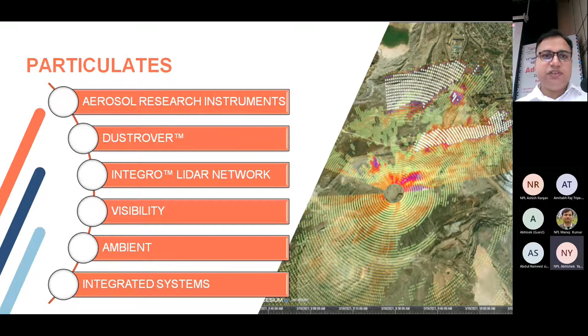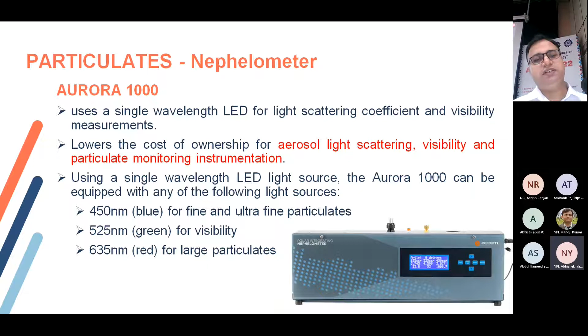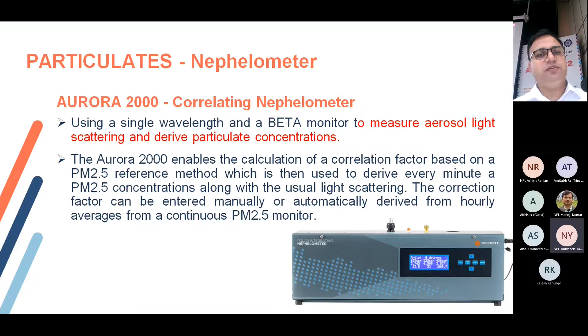Now, there are a few systems which are used for aerosol research. The first one, once again, is the nephelometer, a different model. This particular Aurora 1000 model is used for aerosol light scattering, visibility, and particulate monitoring. It has 3 options, but only one wavelength is used at a time. The 450 nanometer blue light is used for fine and ultrafine particles, 525 is used for visibility, and 635 nanometer is for larger particles. Another one is the 2000. It's a correlating nephelometer, so it measures the aerosol light scattering as well as giving you the particle concentrations for PM2.5.